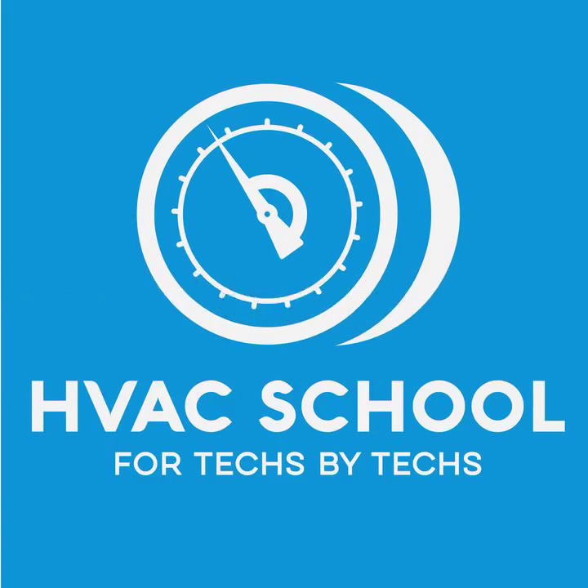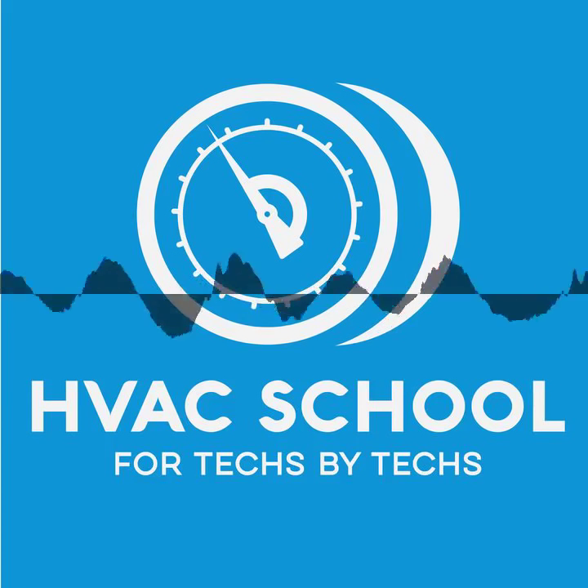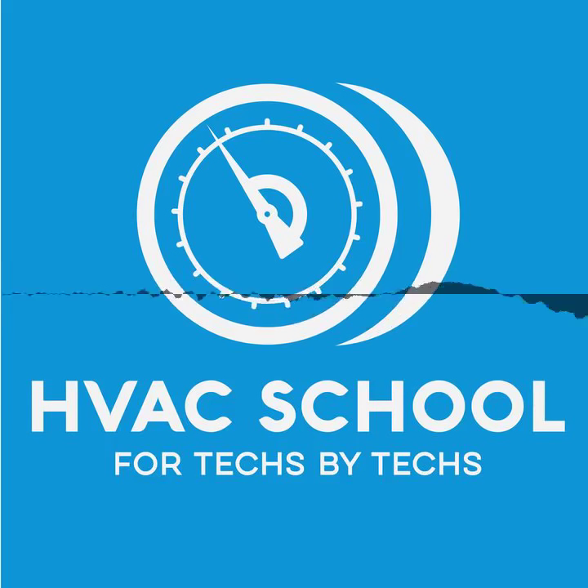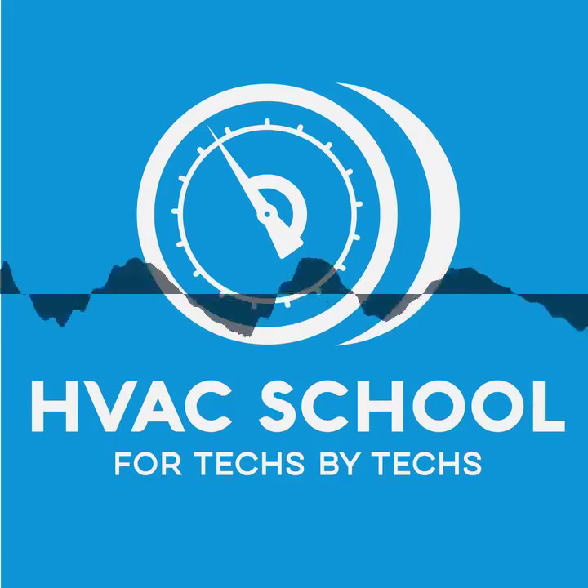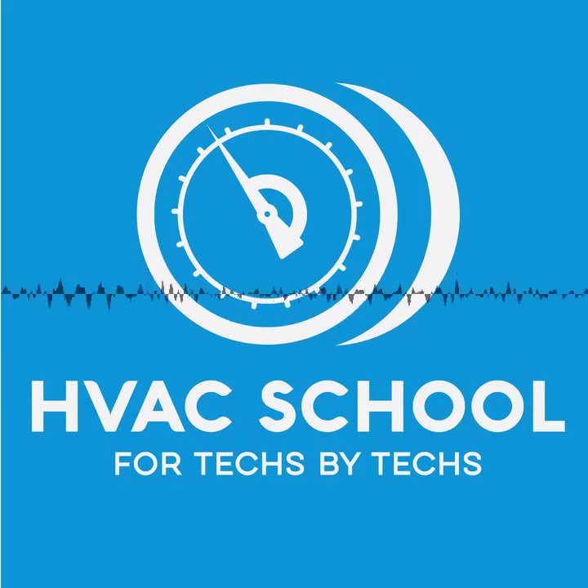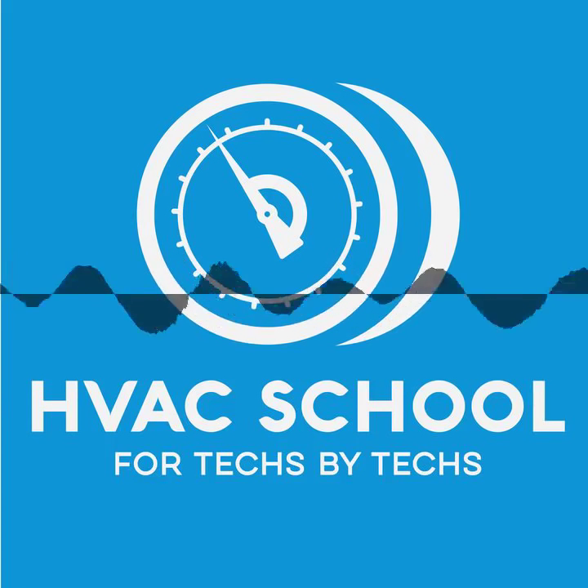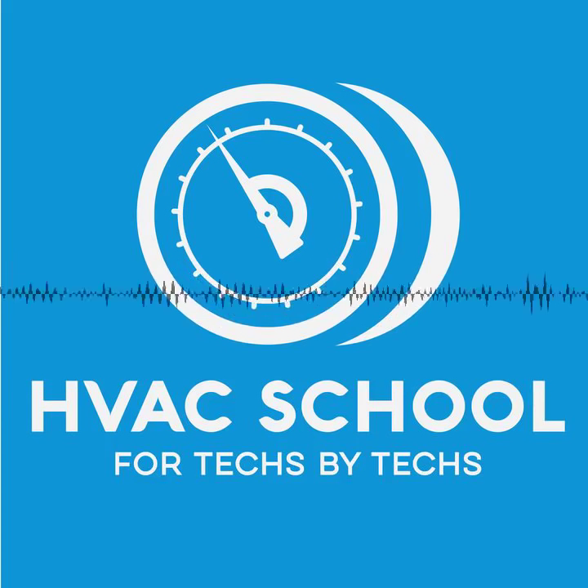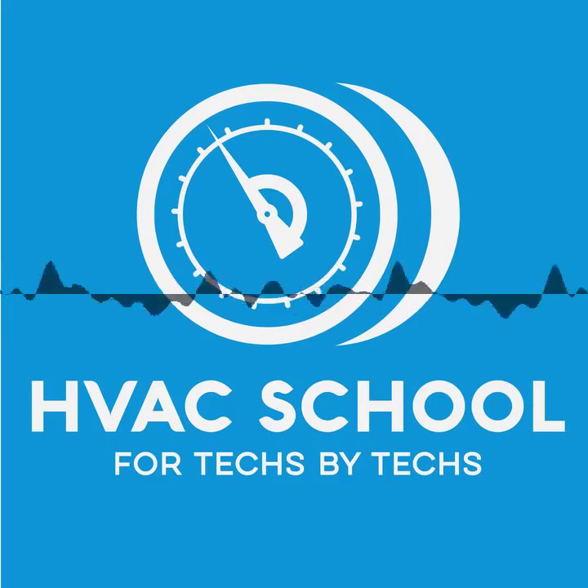Yeah, it's really important because you need to know whether you have a leak or not. On a lot of larger systems, that could be an overnight test. It could be a 24-hour test, could even be 48 hours, whatever it is. You really need to know what you started at, where you are, what the temperature was when you started, and what the temperature is when you ended, and make sure whether you do or you don't have a leak. It's extremely important because it's a whole lot easier than coming back 6 months down the road when you actually do have a leak at operating pressures. We lost a whole bunch of refrigerant trying to find that leak, especially on a VRF system that has hundreds, if not 1,000 different flares.